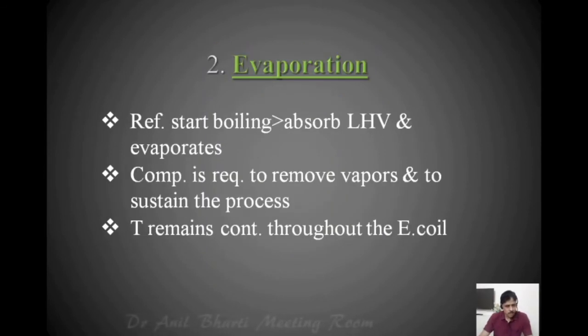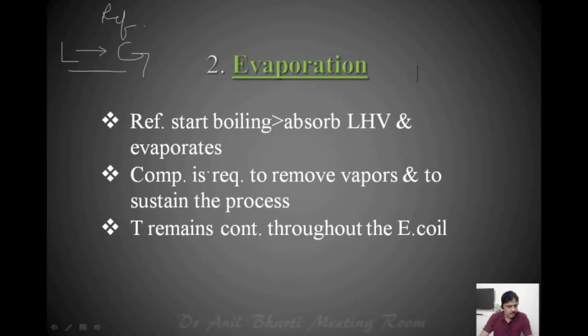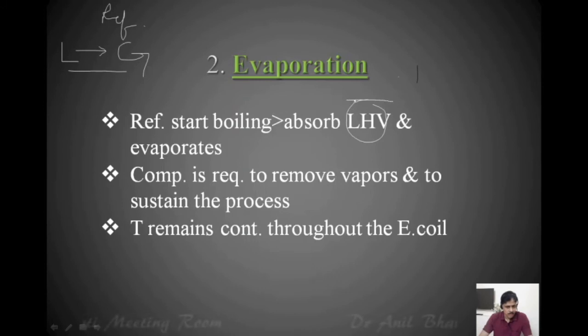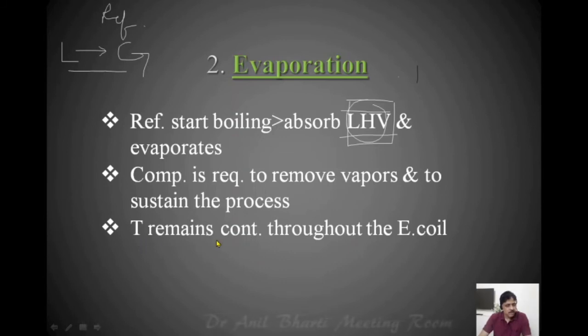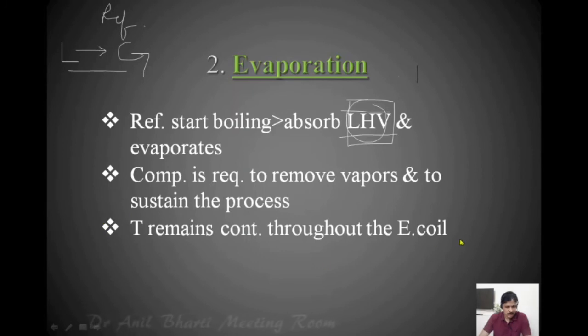The second process is the evaporation process, which means the liquid refrigerant is converting into vapor form — a phase change is happening. When phase change happens, temperature remains constant. So the latent heat of vaporization is absorbed by the refrigerant as it converts from liquid to vapor form, producing the cooling effect. The temperature will be constant throughout the evaporator coil from the very start to the very end. This is a very important characteristic of the vapor compression system — it produces a very even temperature across the evaporator coil.